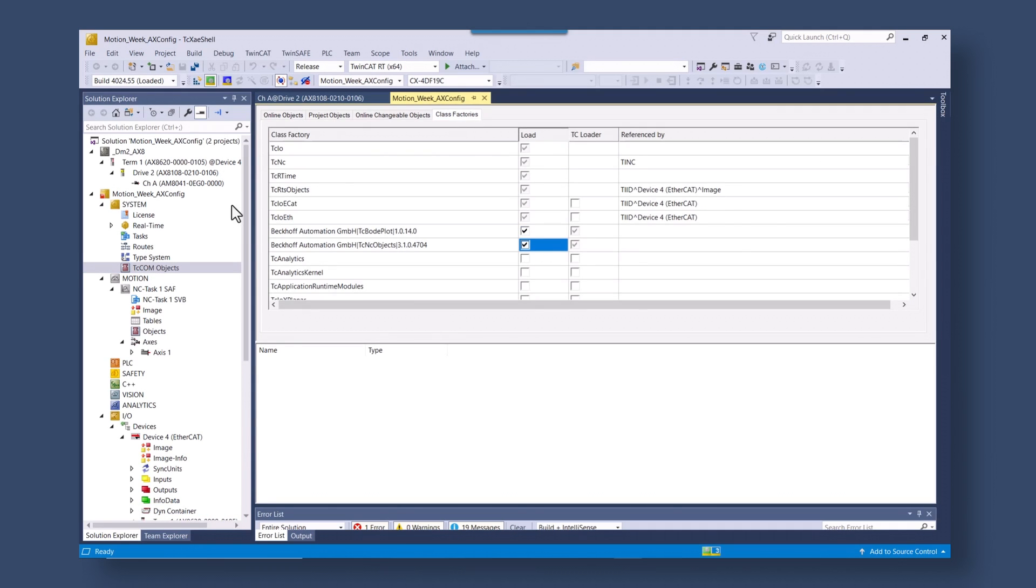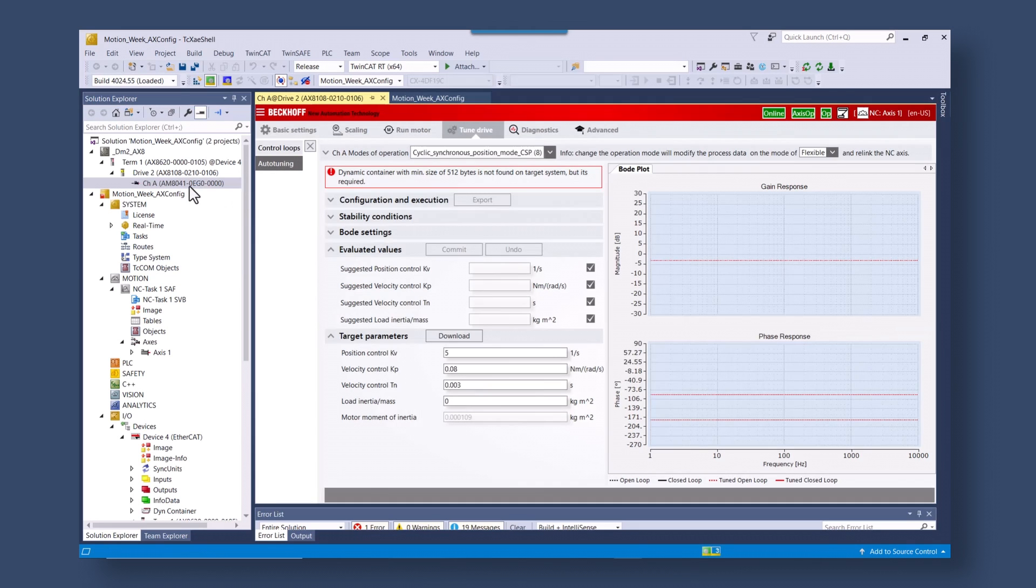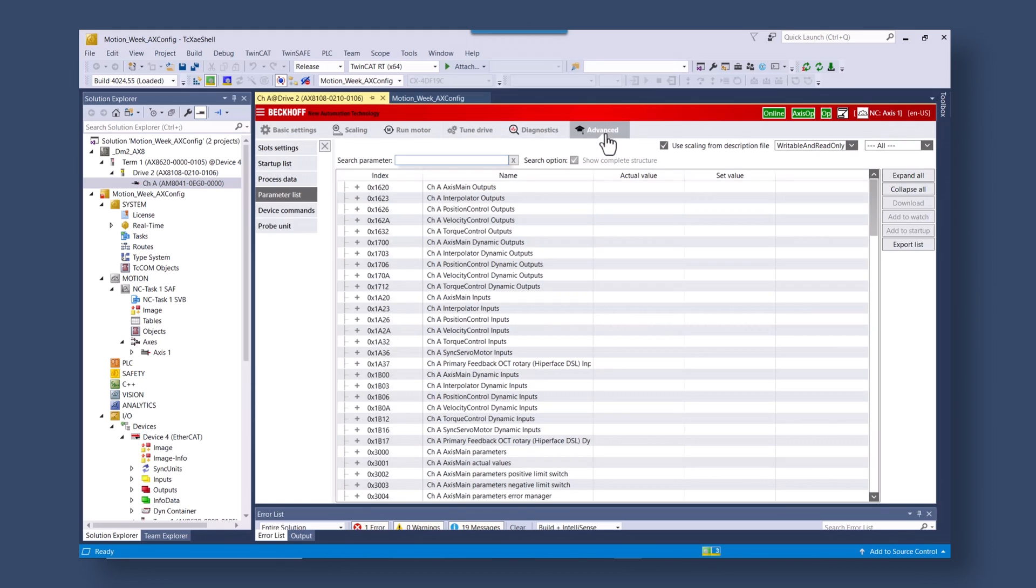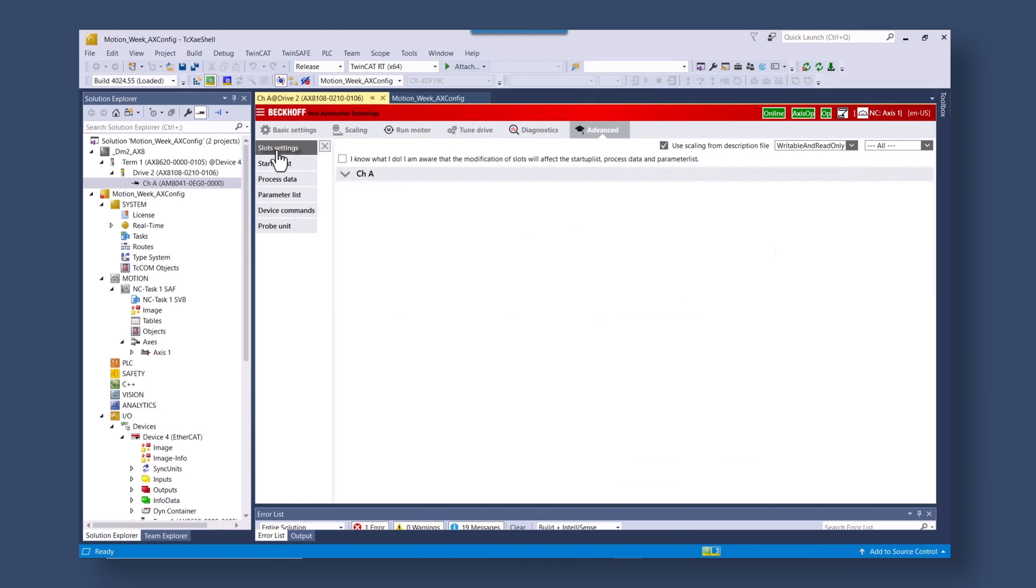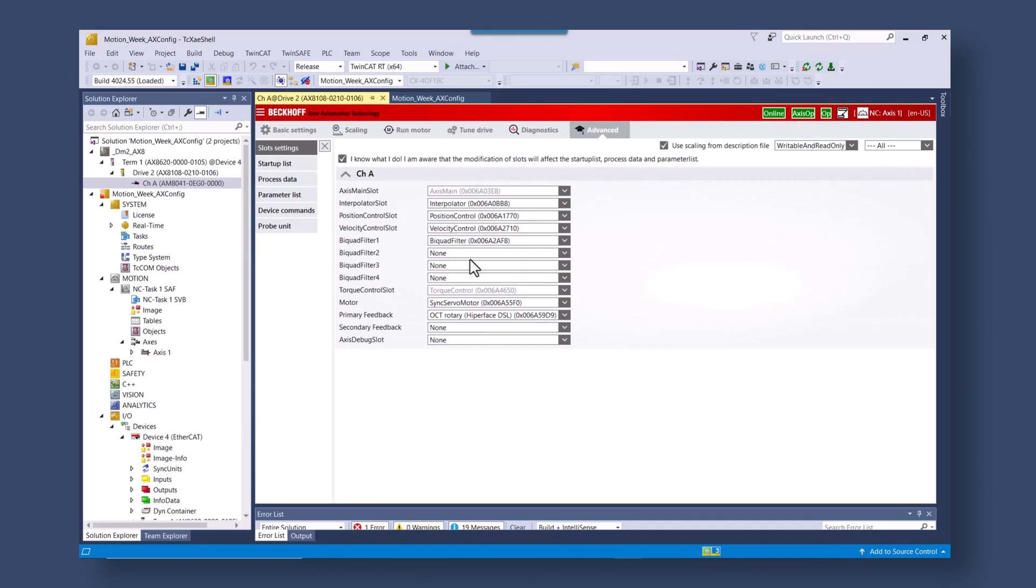We're going to go to the AX8000 axis module. We're going to go under the advanced section. We're going to go to the slot settings and we're going to bring in bi-quad filters in case we need them after running auto tuning.